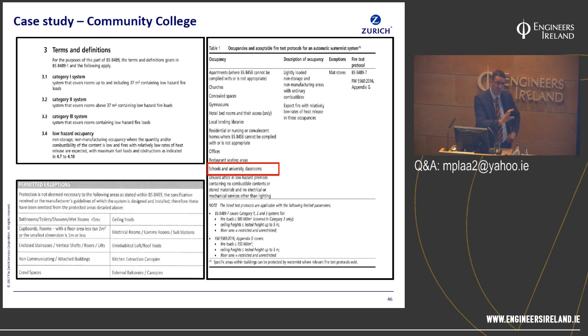So it's important to challenge these designs and have a look a little bit deeper. But this system's already gone in. So what do we do as insurers in this situation? We've got a system where insufficient evidence has been supplied. It's only partial protection. It's only going to be there for life safety, and it can only really be a positive feature. The fire officer, the building control officer may be happy with it, but in reality in a school, the fire alarm's going to go off, everyone's going to be out in four or five minutes, and there is really no life risk. It's about a system being sold as a property protection system, when perhaps in reality it's not.